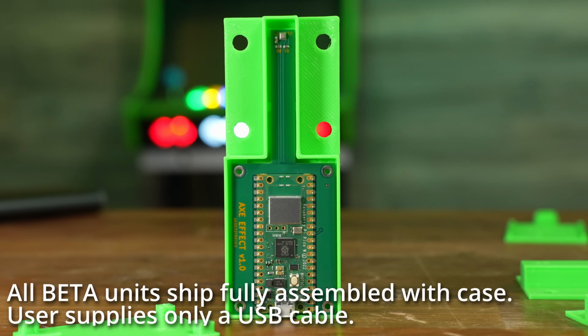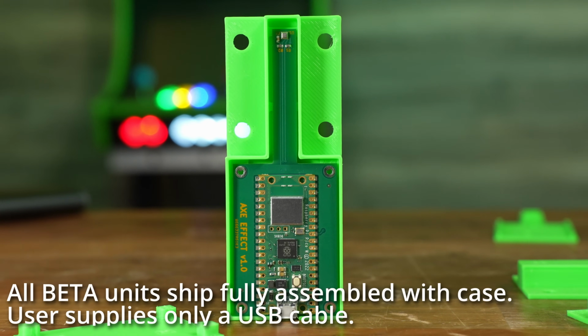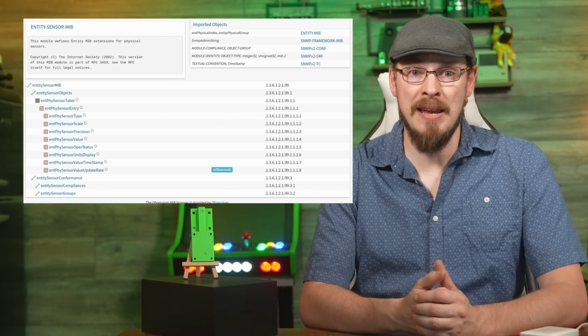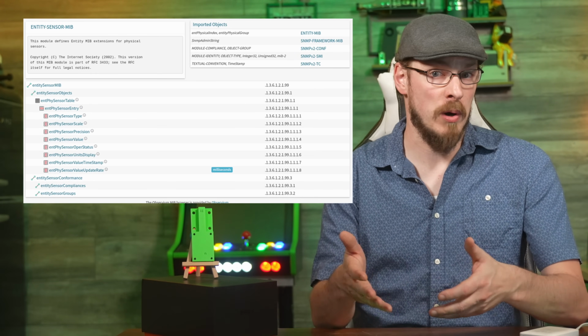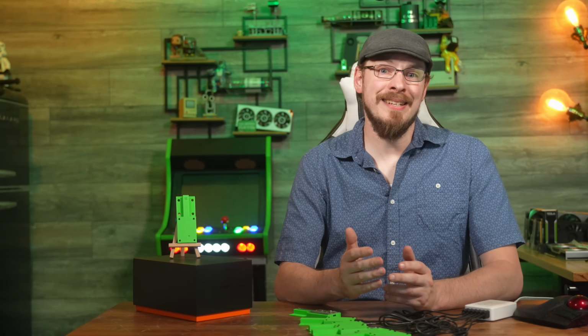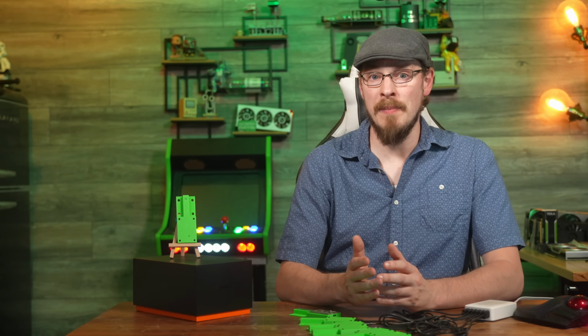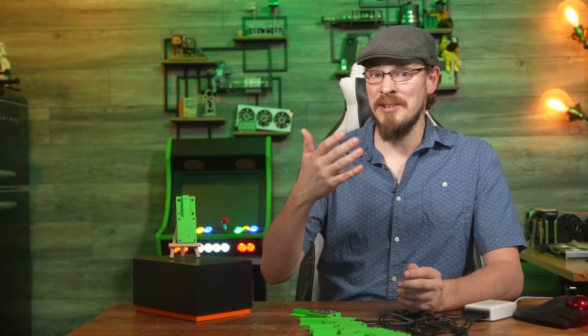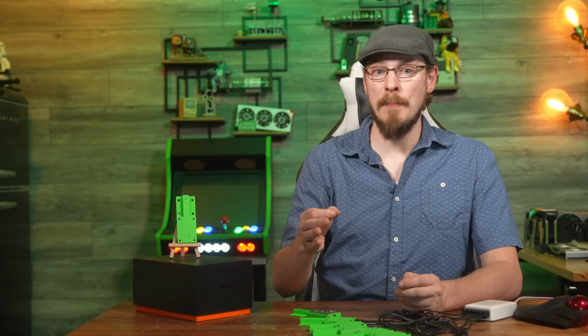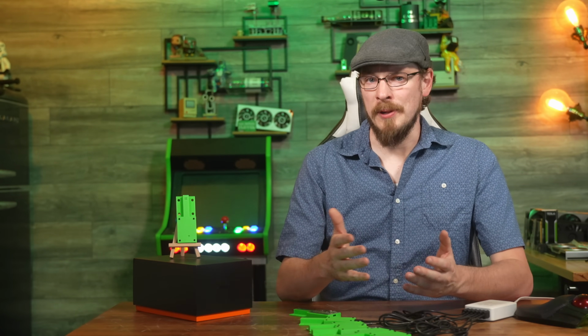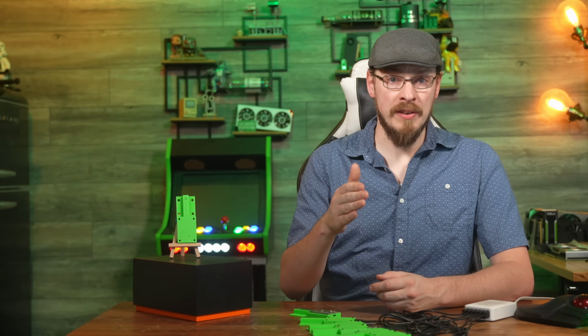It's up to your own SNMP software to take action with that data. Now, I probably don't need to tell anyone this, but SNMP can be something of a nightmare for beginners, especially if the device you want to monitor doesn't use standard OIDs. Lucky for you, we're actually utilizing a standard MIB that's included in most SNMP monitoring software already. AxeEffect reports via the entity sensor MIB, and as long as your SNMP monitoring software isn't stupid, it should auto-detect not only the temperature data, but properly format that data as well. For example, if I jump into Observium, all I need to do is add the device, specify the SNMP v2c community name, and the temperature sensor is automatically created.